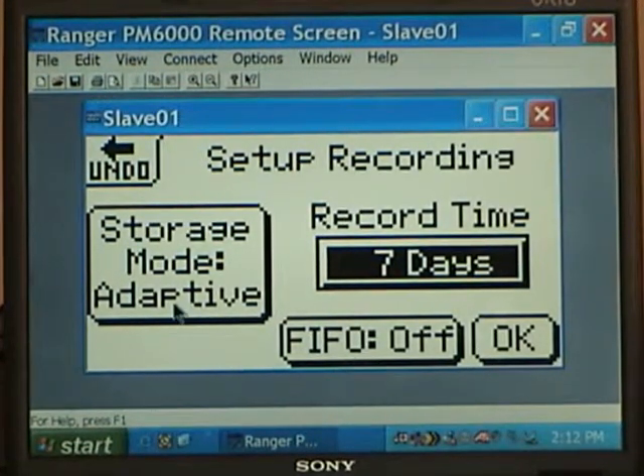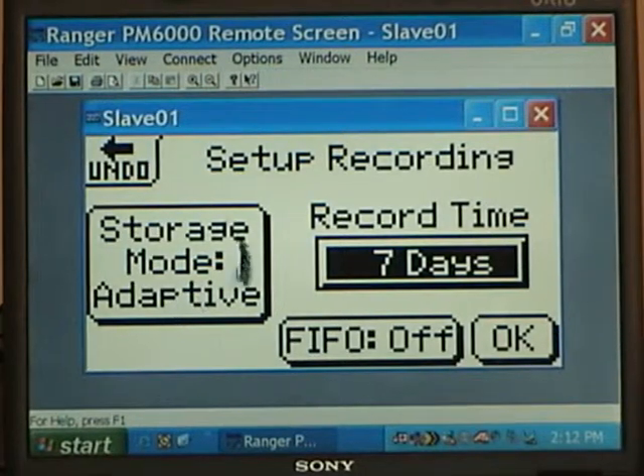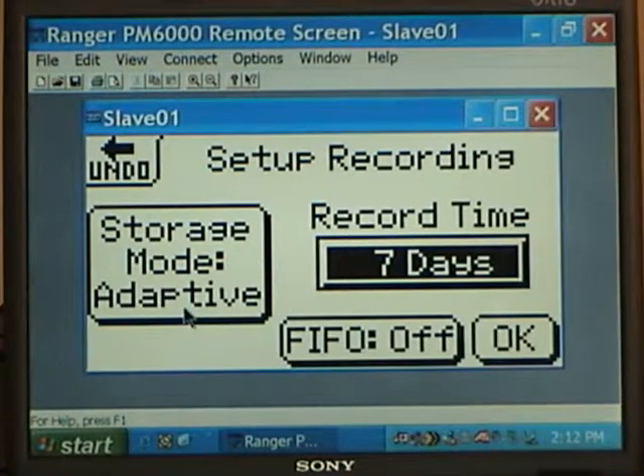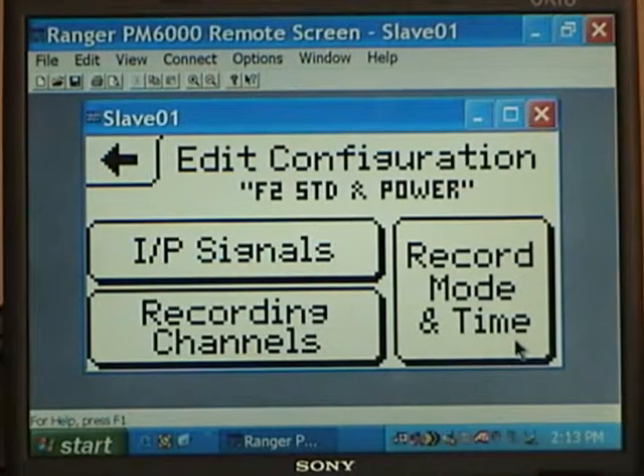The storage mode is adaptive store, single cycle adaptive store. We can't stress enough, this is our patented storage technique, which allows us to record for long periods of time and still give you single cycle resolution on RMS data, regardless of the time of the recording, within reason, 30 days or less typically. We'll just say OK, we'll leave it here at that.